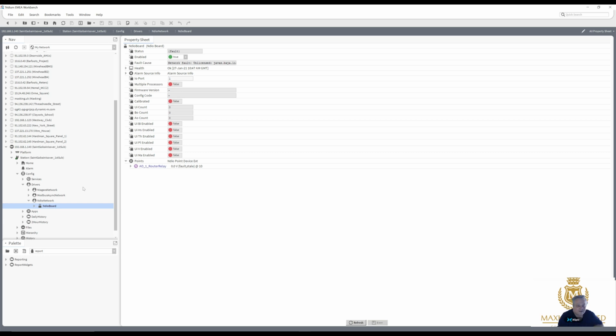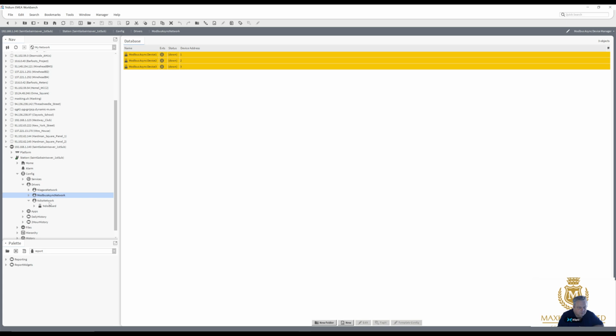Okay, well, that's how we change AX to N4, and if we have got a module that doesn't exist, or it's a third-party module, how we delete it by editing the config.bog file, which people normally don't tell you how to do.